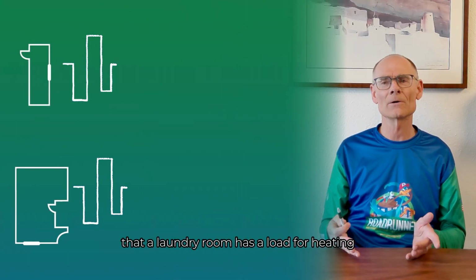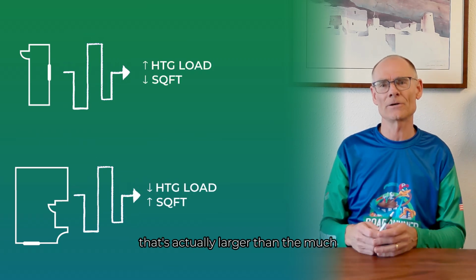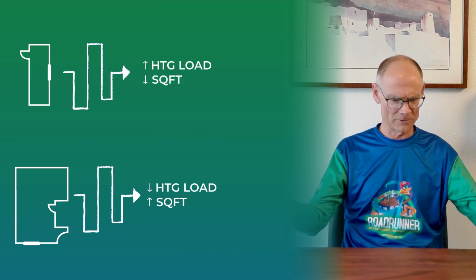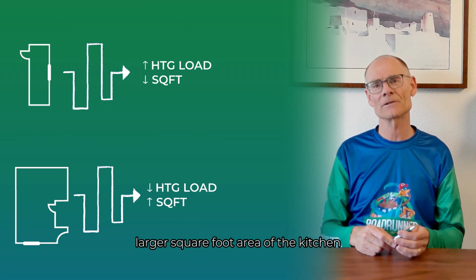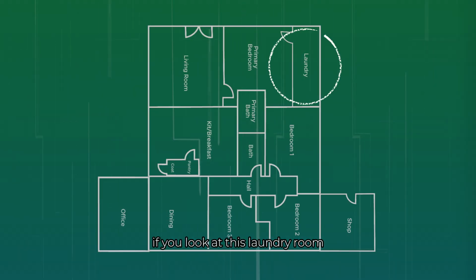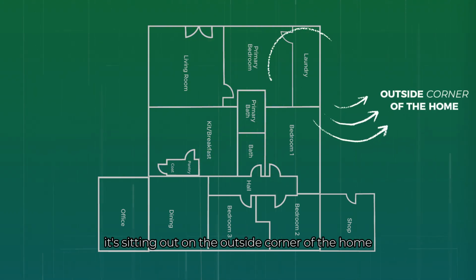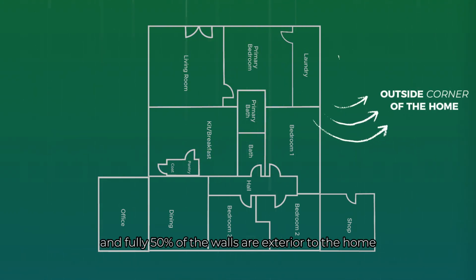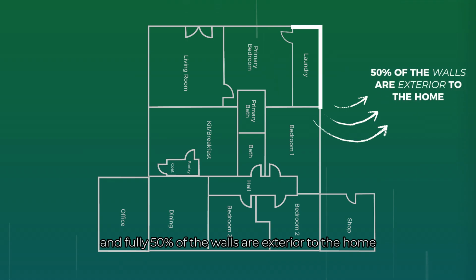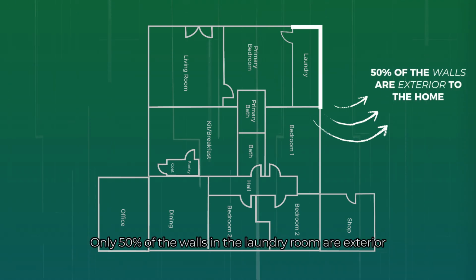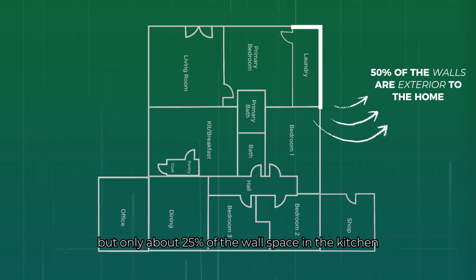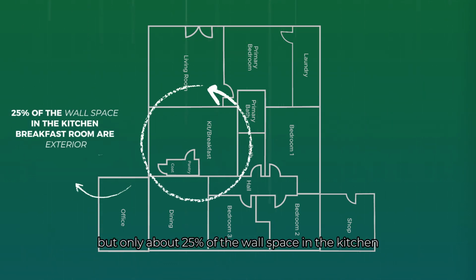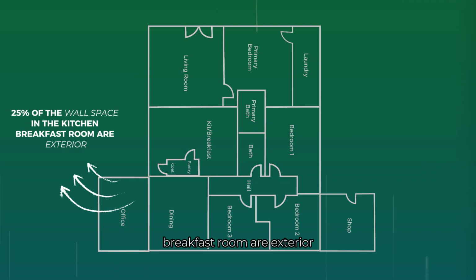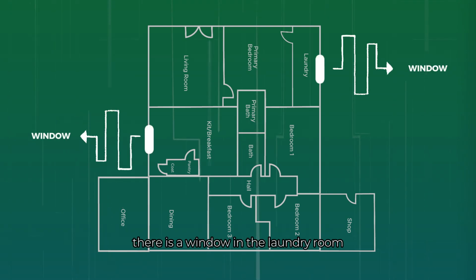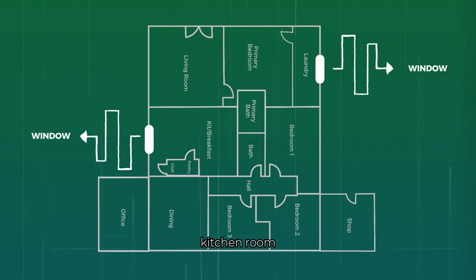So how can this be, that a laundry room has a load for heating that's actually larger than the much larger square foot area of the kitchen breakfast room? If you look at this laundry room, it's sitting out on the outside corner of the home, and fully 50% of the walls are exterior to the home. Only about 25% of the wall space in the kitchen breakfast room is exterior. There is a window in the laundry room and a window in the kitchen breakfast room.